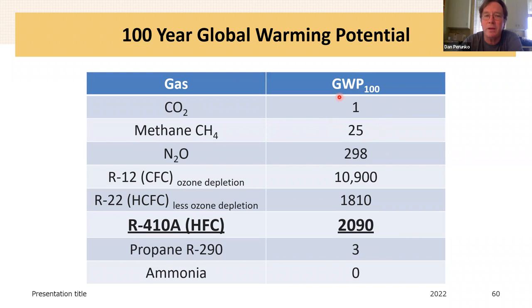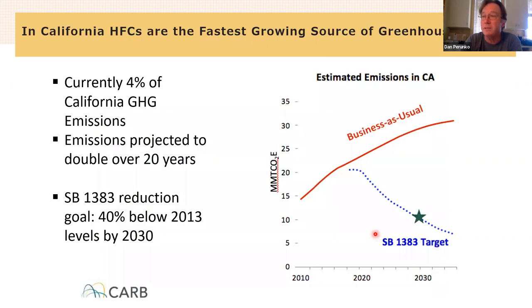Right, we talk about carbon and methane all the time as the global warming people. Carbon is at a global warming potential at 100 years at 1. Methane is at 25. Nitrous oxide, which also comes from combustion, is at 298. R12, which is a refrigerant we stopped using because of ozone issues, was really bad. It was at 10,000. R22 is a refrigerant we stopped using because of ozone issues. It was at 1,800. Our current refrigerant that we're using is at 2,090. I said 2,088 before. Depending on where you look, it varies a little bit, but it's over 2,000, right? So 2,000 times worse than carbon. We can't afford to release it at all.